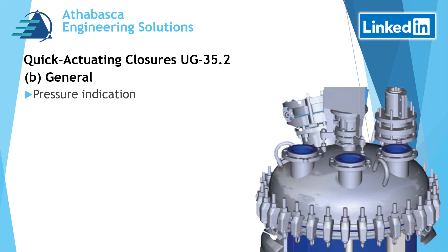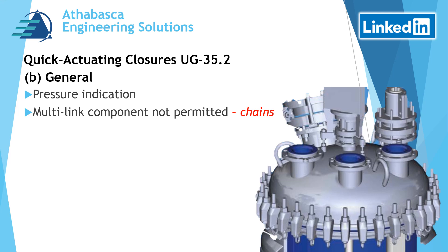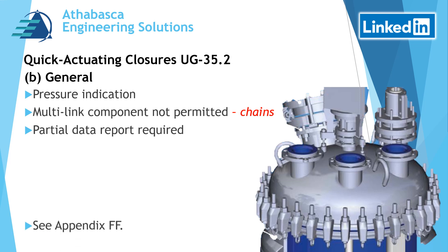There must be some kind of pressure indication — for example, a pressure gauge on the assembly is required. Multi-link components such as chains are not permitted for quick opening closures. A partial ASME data report is required for this type of design. Appendix FF contains instructions about operating procedures and conditions required to design a quick actuating closure.